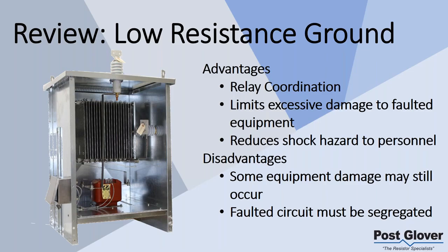Well, if you have a few thousand, you're probably going to want to trip as fast as possible, because that's going to cause excessive damage to your system. That means that your coordination time is hampered. Basically, from a relay perspective, you need to trade off between very fast or instantaneous tripping and risking some relay or coordination issues, or you accept more damage.